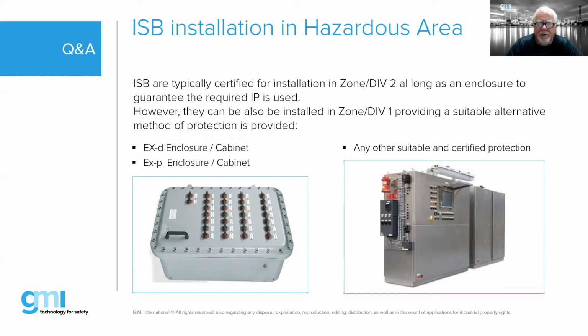But most barriers that you will find in the marketplace, including GMI's products, are suitable for output into a zone 0 area, but are designed to be installed into a zone 2. So they're dual marked, if you will. They'll be EXNA, or to the new marking requirements, I think it's EXEC. Basically, they can be mounted into a zone 2 as long as they're in a suitably approved EXN type enclosure, generally speaking. Now that's generals. Look at the specific wiring regs in your country to make sure.